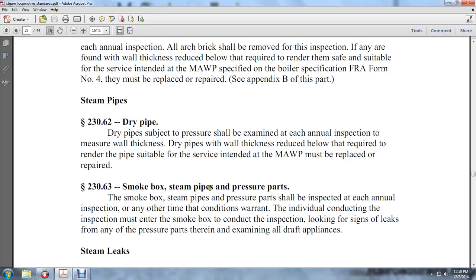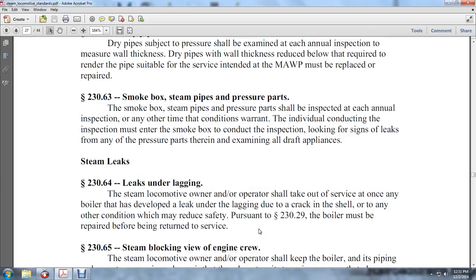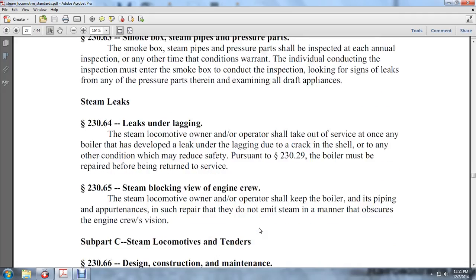Smoke box steam pipes and pressure parts shall be inspected at each annual inspection and at any other time conditions warrant. The individual conducting the inspection must enter the smoke box to locate signs of leaks in any pressure parts and to examine all draft appliances.